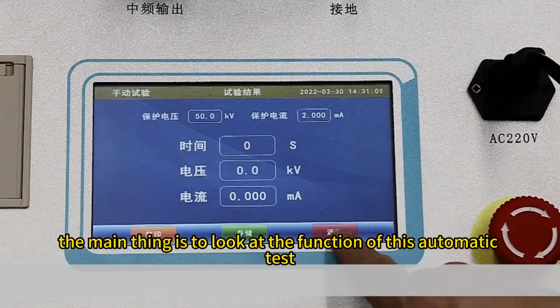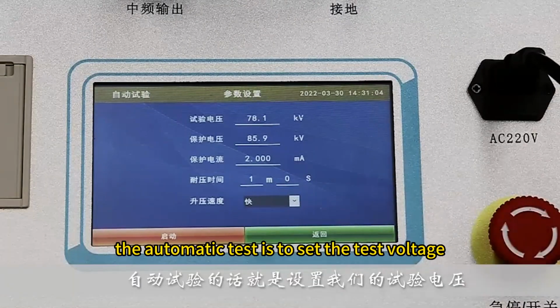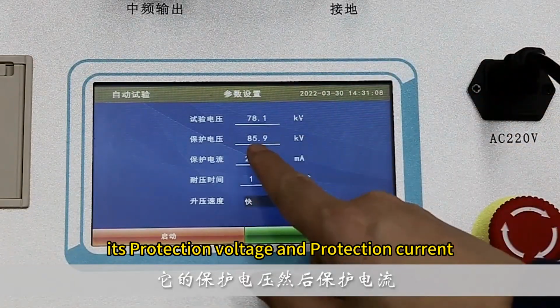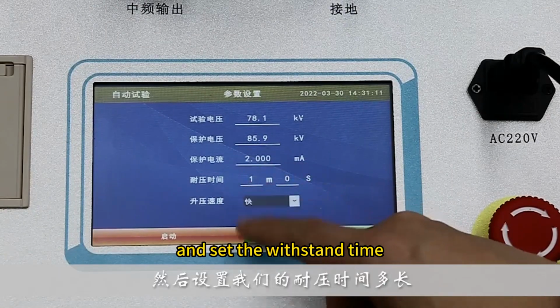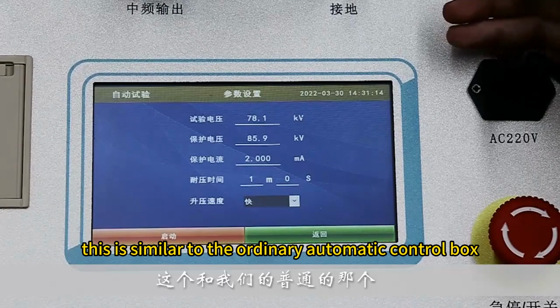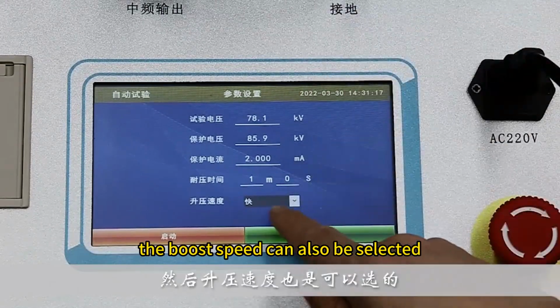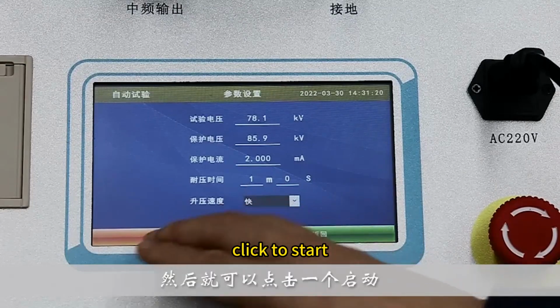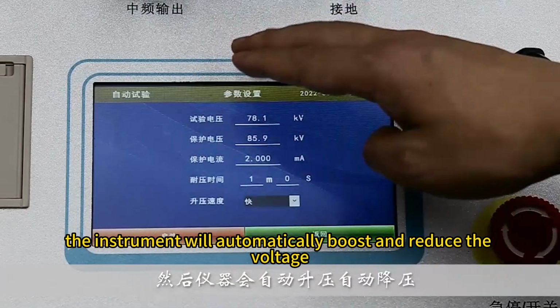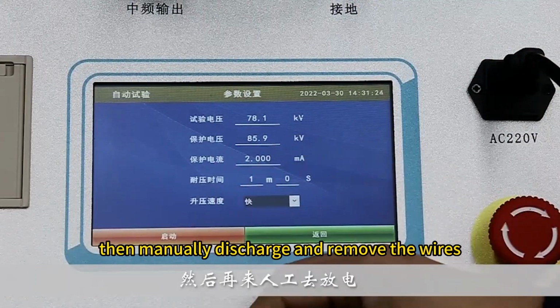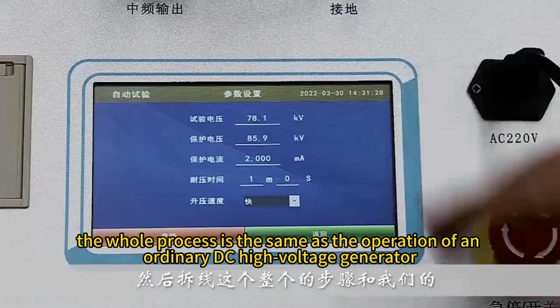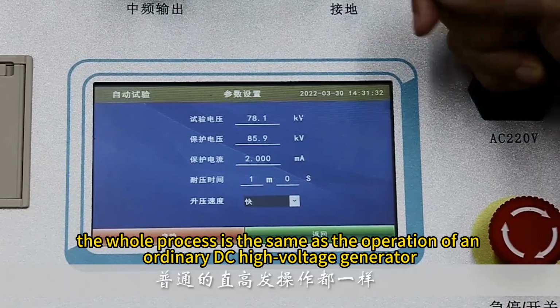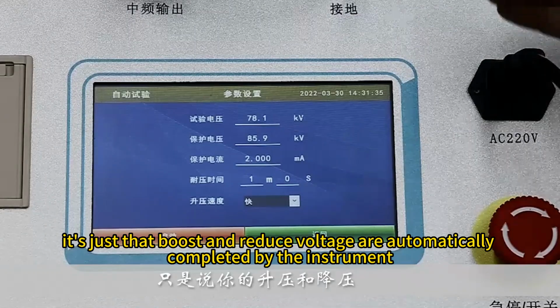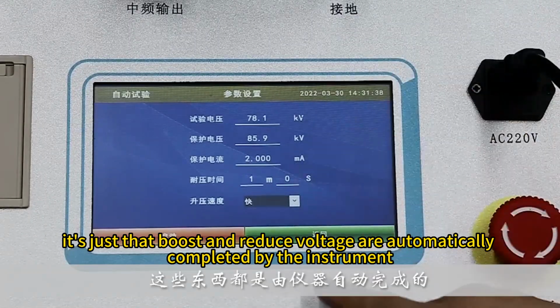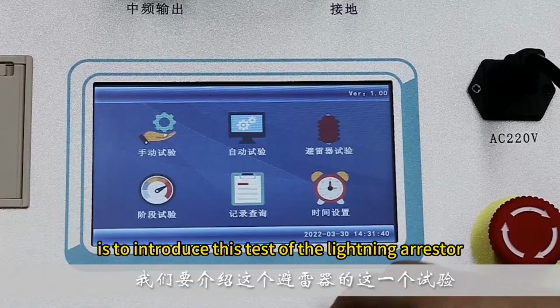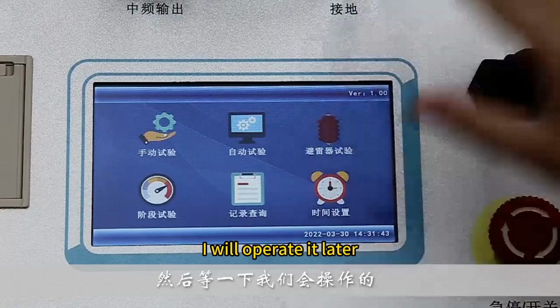The main thing is to look at the function of this automatic test. The automatic test is to set the test voltage, its protection voltage and protection current, and set the withstand time. This is similar to the ordinary automatic control box. The boost speed can also be selected. Click to start. The instrument will automatically boost and reduce the voltage. Then manually discharge and remove the wires. The whole process is the same as the operation of an ordinary DC high-voltage generator. It's just that boosting and reducing voltage are automatically completed by the instrument. The key point is to introduce this test of the lightning arrestor. I will operate it later.